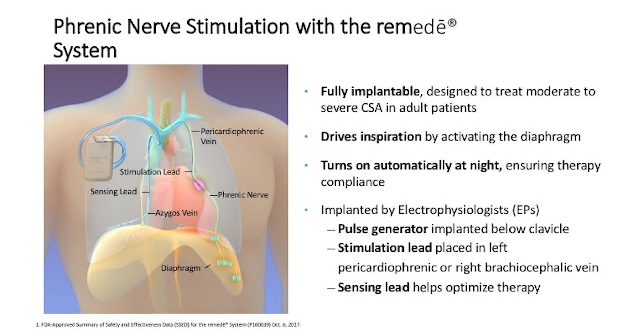It's implanted by electrophysiologists. First, a pulse generator is implanted below the clavicle, and then both a stimulation lead and a sensing lead are placed during the implant procedure. This enables the device to sense respiration as well as patient movement and location, and combined makes the device fully automatic. The remedē system, based on the results of the pivotal trial, was approved in October of 2017 as the first of its kind proven alternative for central sleep apnea treatment.